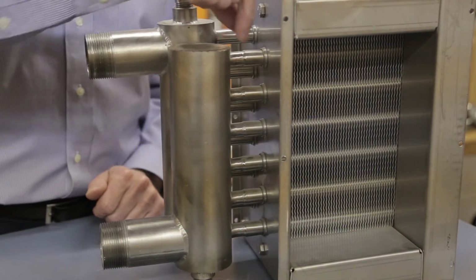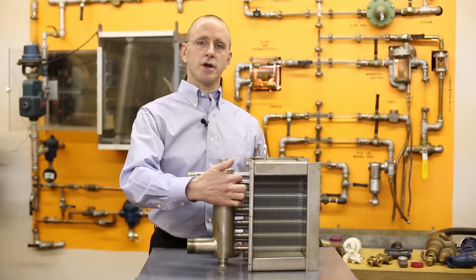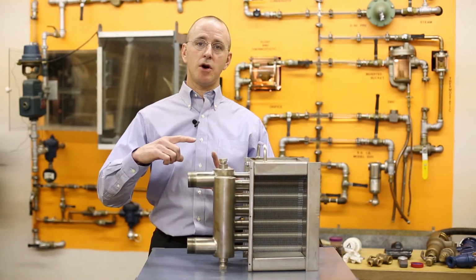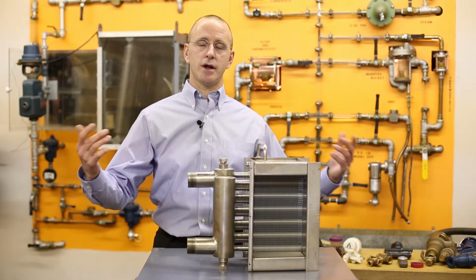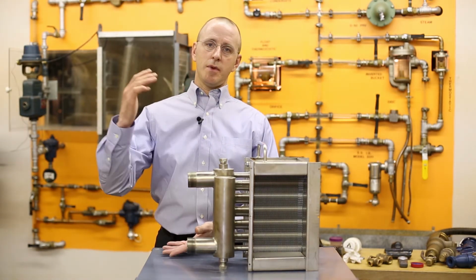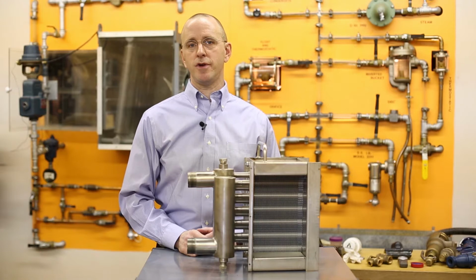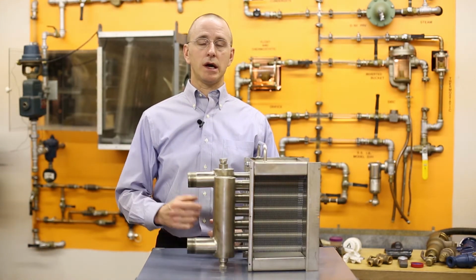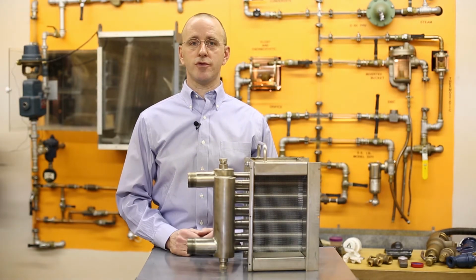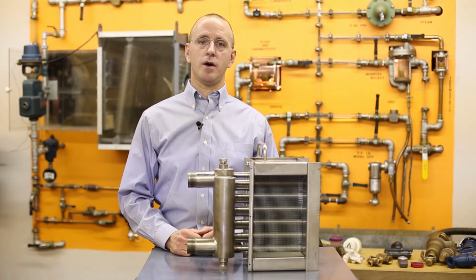When looking at tube diameter, there's many different things that can come into play. If you've got a small coil, we would typically look at smaller diameter tubes, whereas if you've got a much larger coil, maybe 90 inches tall by 20 or 30 feet long, we would typically look at a larger diameter coil. Again, you're looking at fluid velocities and fluid pressure drop, where we'll help make that selection.